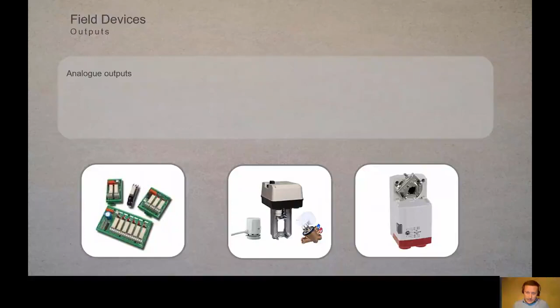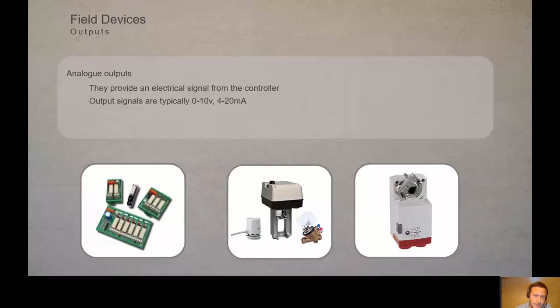Moving to the outputs now, analog outputs. To be honest, it's very similar to the inputs. We have analog outputs that normally range from 0 to 10 volts DC. So for a valve actuator, if we want the valve to open to 80%, that equates to 8 volts. For 50%, it's 5 volts, and so on. It directly proportionally scales the voltage to a percentage output. You can offset some of these, but in general a 0 to 10 volt output provides a 0 to 100% output. That can also be driven by milliamps, scaling the same way, typically 4 to 20 milliamp.